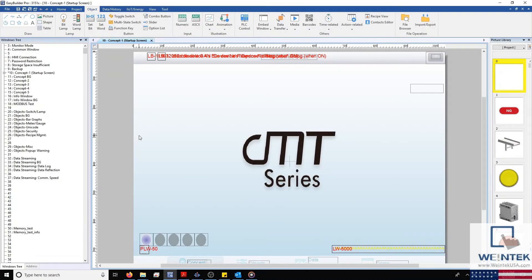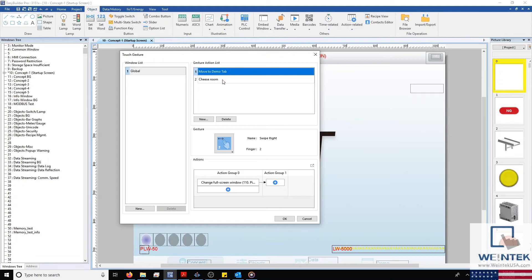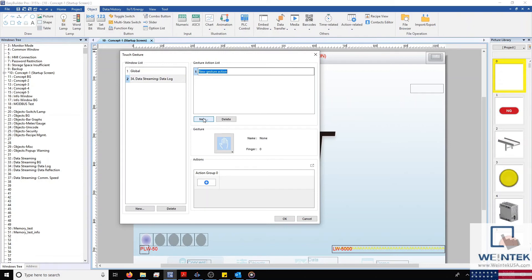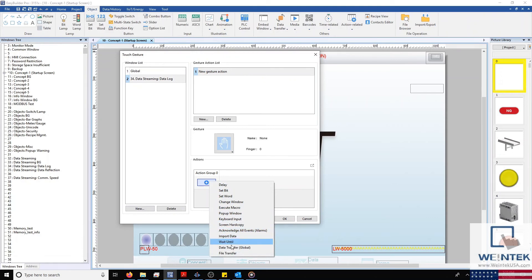Perhaps that wasn't the most exciting use of our touch gestures, but you may be asking what other actions can we perform. Because this is a very long list, a visual demonstration is the best way to introduce this exciting feature. With EasyBuilder Pro open, I'm going to select our object tab, and under action related, I'll select our touch gesture object. What I have configured currently are global touch gestures, but we can easily create a new object and configure touch gestures that are window specific. Within each object we can have up to 16 separate gestures, and within each gesture we can have up to 23 sequential actions, which will allow an operator to perform simple or complex tasks by simply performing a specific touch gesture.